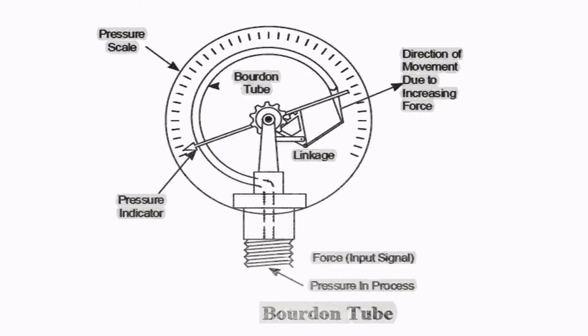You can see the working of a Bourdon tube here. The pressure enters the inlet of the C-tube, and the C-tube gets expanded. This causes the linkage to move, which in turn causes the quadrant-pinion arrangement to move, and that causes the pointer to move on the dial gauge. This is how the Bourdon gauge works — the primary sensing element is an elastic tube, typically made of stainless steel, and the pressure is converted into a mechanical movement. This is called a deformation gauge.